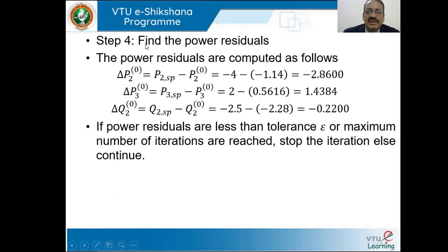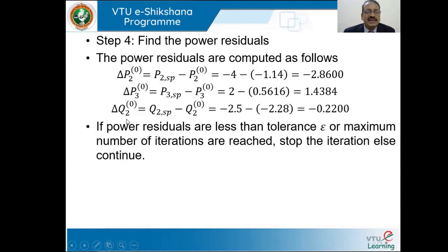In step 4, we compute the power residues. ΔP2⁰ = P2 specified − P2⁰ = −4 − (−1.14) = −2.86. ΔP3⁰ = P3 specified − P3⁰ = 2 − 0.5616 = 1.4384. ΔQ2⁰ = Q2 specified − Q2⁰ = −2.5 − (−2.28) = −0.22.